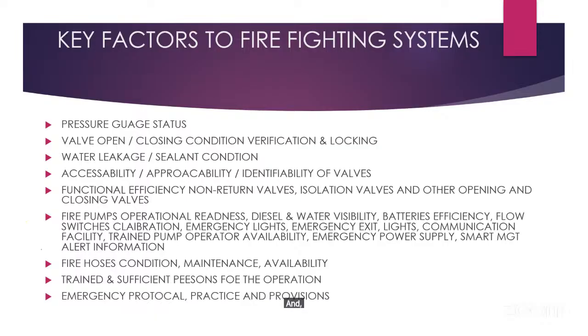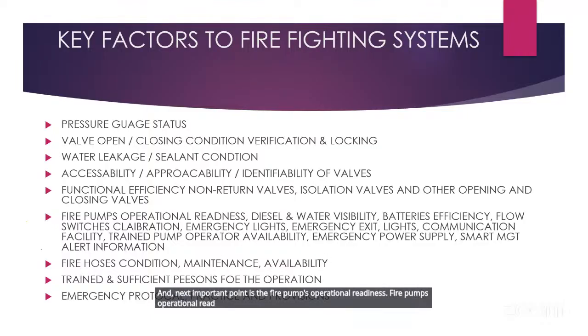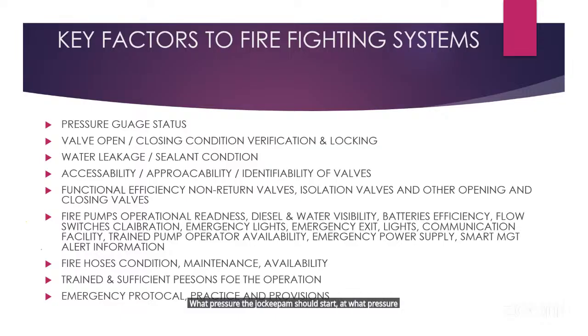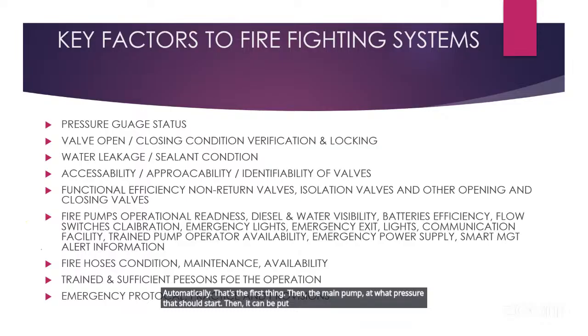The next important point is the fire pump's operational readiness. There is a testing procedure. You must put a pressure matrix in the pump room: at what pressure the jockey pump should start and at what pressure it should stop automatically. Then the main pump: at what pressure it should start, and it can be switched off only manually. And the standby pump: at what pressure it should start. That pressure difference must be there. Accordingly the pressure switches must be designed and connected to the fire pumps, and they must work in sequence. That is the operational functional testing and readiness of the pump.